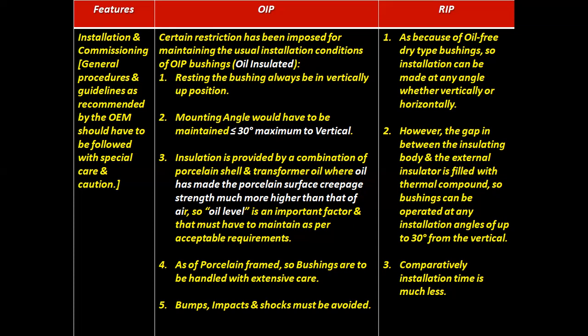So, oil level is an important factor and must be maintained as per acceptable requirements. Before installation, you have to check it. As it is porcelain framed, the bushings are to be handled with extensive care. Bumps, impacts, and shocks must be avoided.